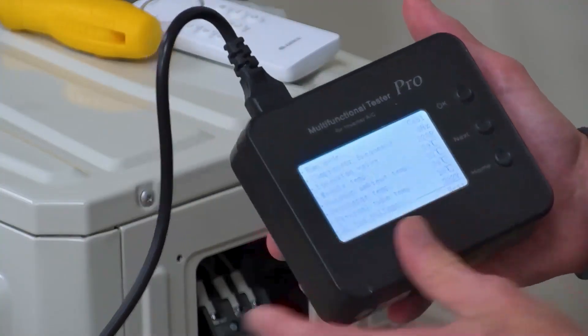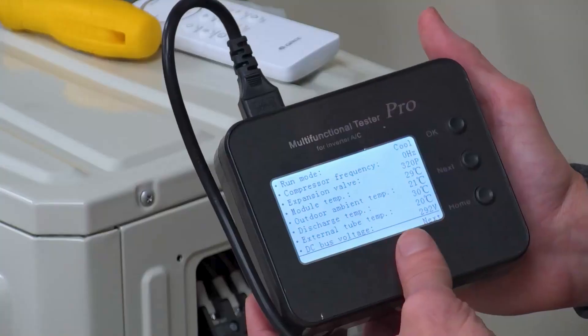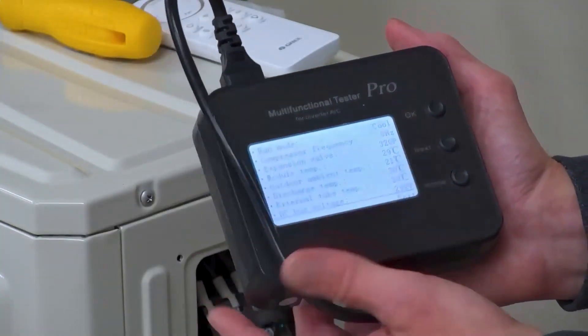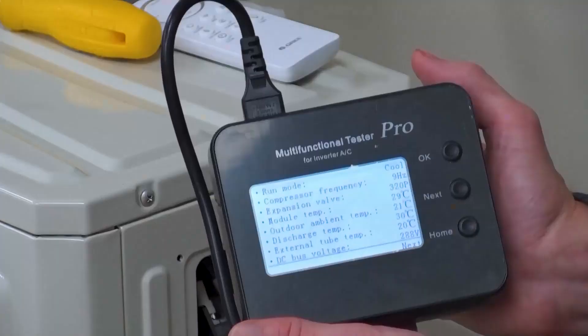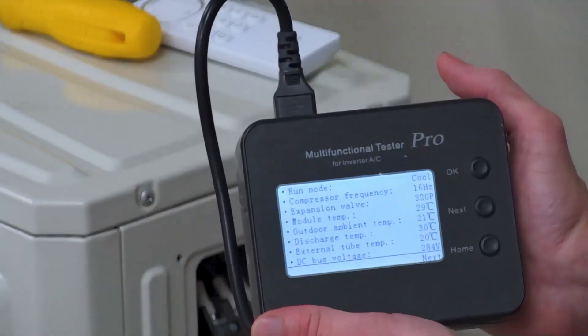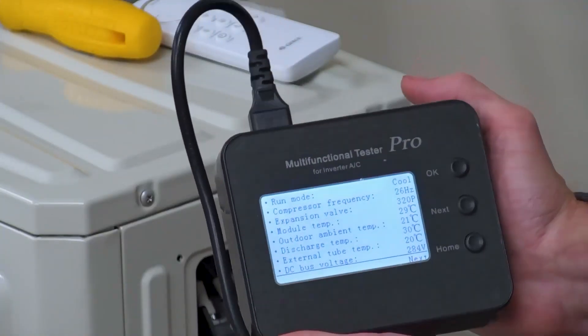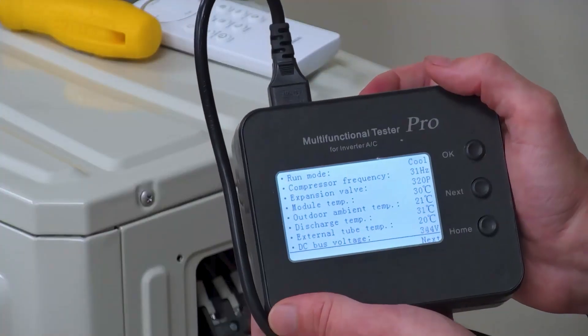The condenser just came on. We are in cool mode. What we're doing is waiting for that compressor to come on. Once the outdoor unit fully comes on, we know the issue is not in the outdoor unit. Then we can disconnect this tool and connect to the indoor head and act as the outdoor unit to bring on the indoor head. Looks like the compressor just came on — we have a compressor frequency.